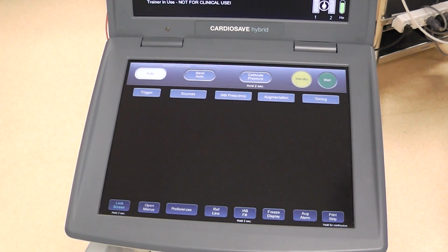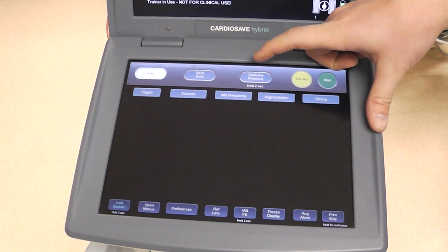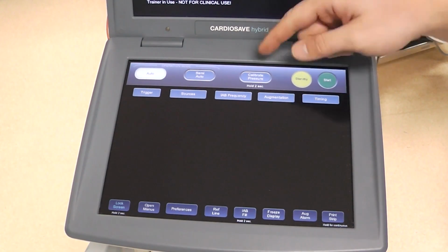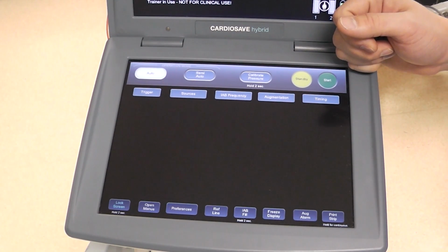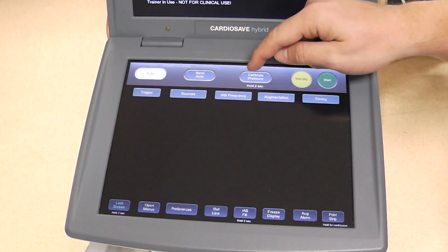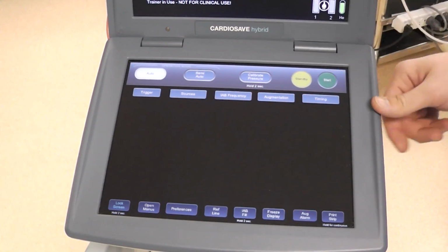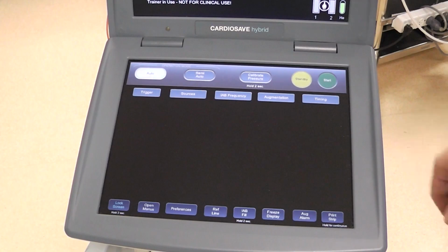If you are using a separate monitor, if your balloon catheter does not have the fiber optic connection, then you will need to zero your transducer. And you do that exactly the same way you do with every other transducer. You open it to atmosphere, and then to zero it, you will hold down this calibrate pressure button for 2 seconds.